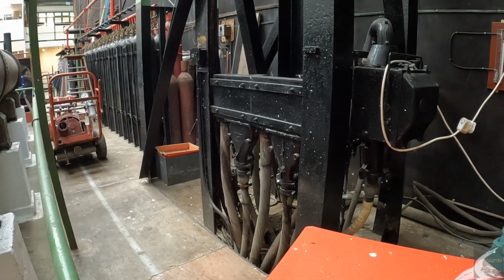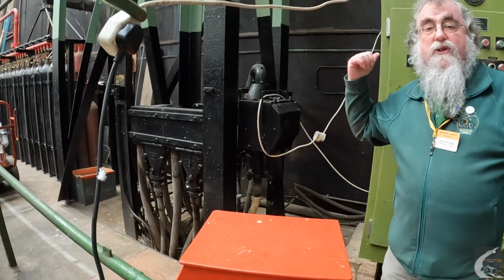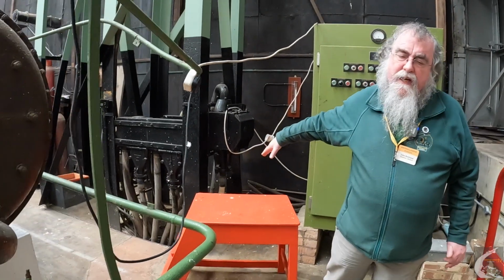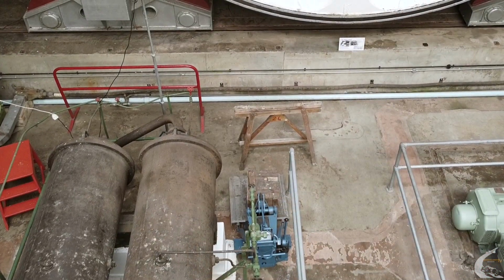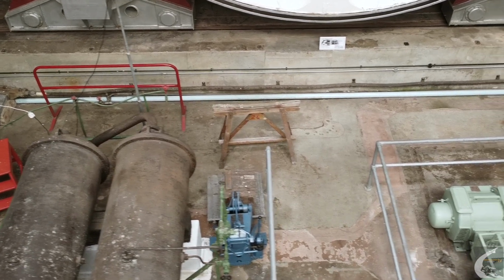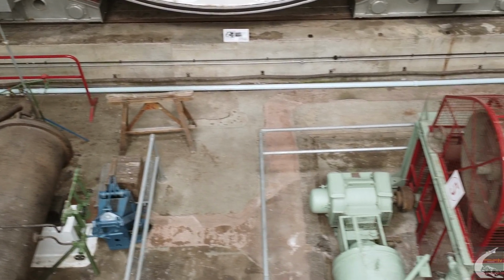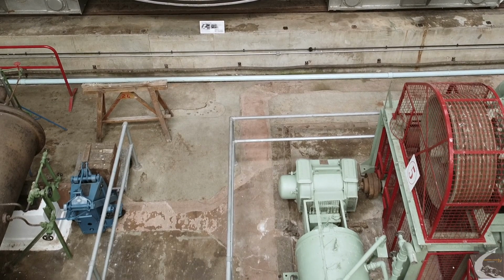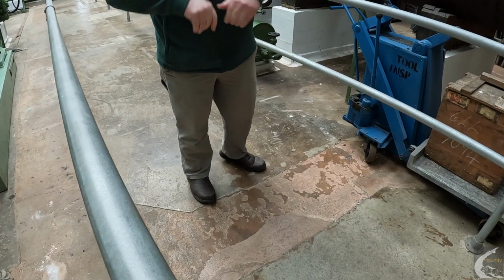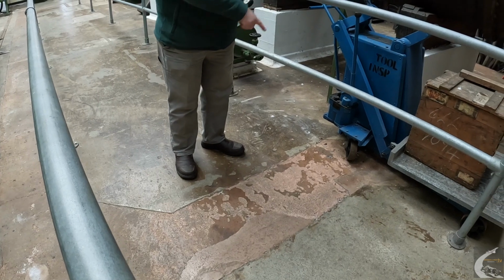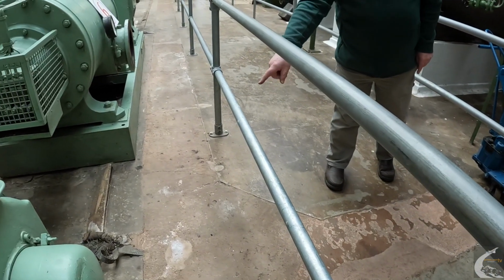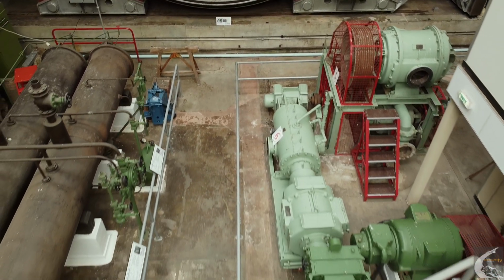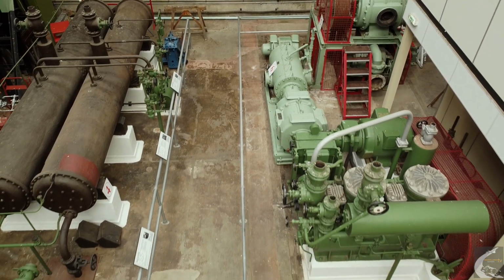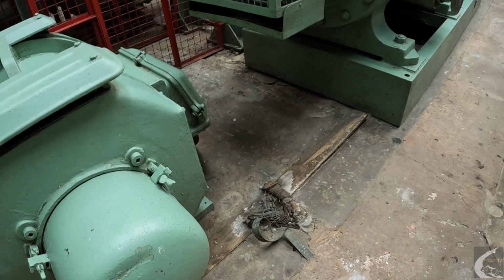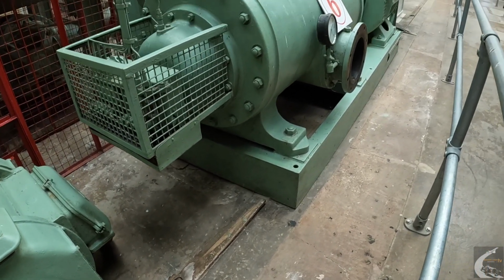Now the main power feed would have come across through to the plant control room, and then there will be a set of cables coming back. If we look at the floor in the middle here, you may see that it's got 2 angles on it, and I suspect that is because you had main power coming in and then coming round. Given how tight these cables are, you can't put small bends on them, so it'll have a large bend going through, and then the cables coming back, which were powering the plant in here, would be coming back through here. One of them went straight on there, but the others would come through here. So there is a connection there which would have been for the other of the compressor units, of which we have 2 of the 4.